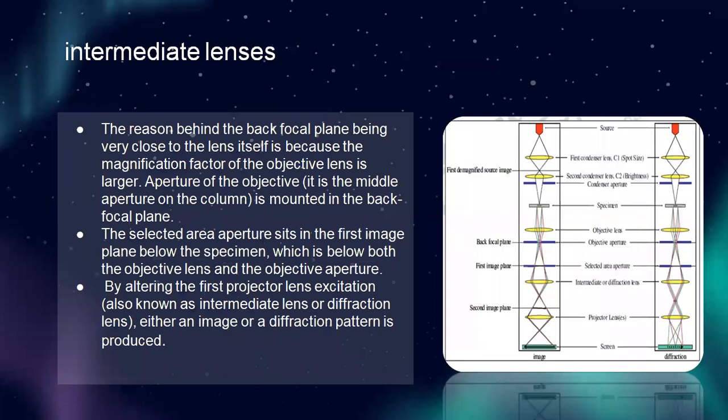Next, I will discuss intermediate lenses. The reason why the back focal plane is very close to the lens itself is because the magnification factor of the objective lens is large. The aperture of the objective lens — the middle aperture on the column — is mounted in the back focal plane. The selected area aperture sits in the first image plane below the specimen, below both the objective lens and the objective aperture. By altering the first projector lens excitation — also known as the intermediate lens or diffraction lens — either an image or diffraction pattern is produced.